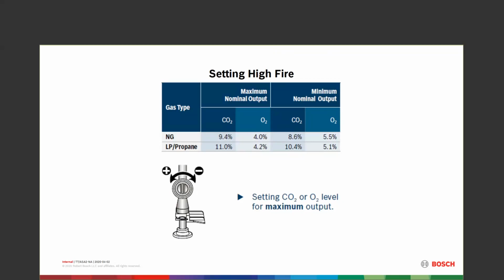and high fire. And what I can tell you is that you're going to go back and forth just a little bit. Don't take big bites with this. An eighth of a turn on this high fire adjustment is big. That'll get you a full or maybe even 2% CO2, so full percentage points. You might go from 11 to 9 or 11 to 13% CO2 in there. So watch out for that. For me, it's about the width of a dime.